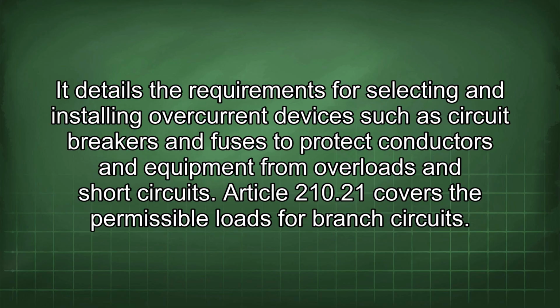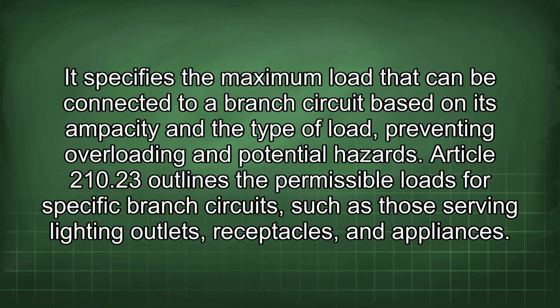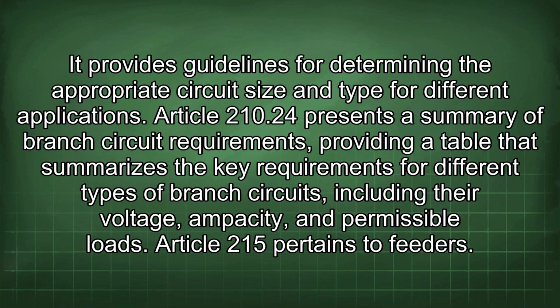Article 210.21 covers the permissible loads for branch circuits. It specifies the maximum load that can be connected to a branch circuit based on its ampacity and the type of load, preventing overloading and potential hazard. Article 210.23 outlines the permissible loads for specific branch circuits, such as those serving lighting outlets, receptacles, and appliances. It provides guidelines for determining the appropriate circuit size and type for different applications. Article 210.24 presents a summary of branch circuit requirements, providing a table that summarizes the key requirements for different types of branch circuits, including their voltage, ampacity, and permissible loads.